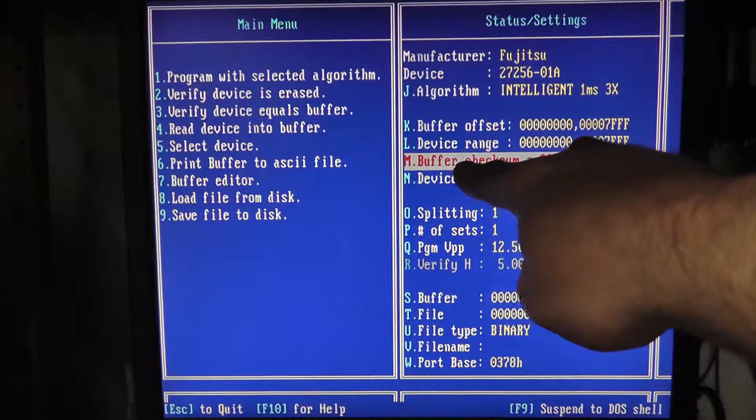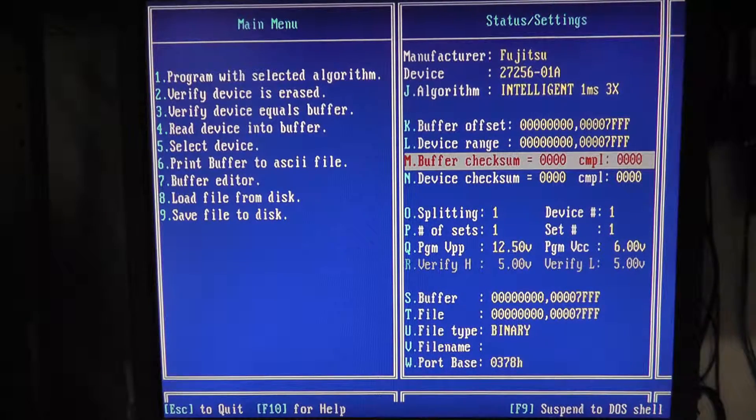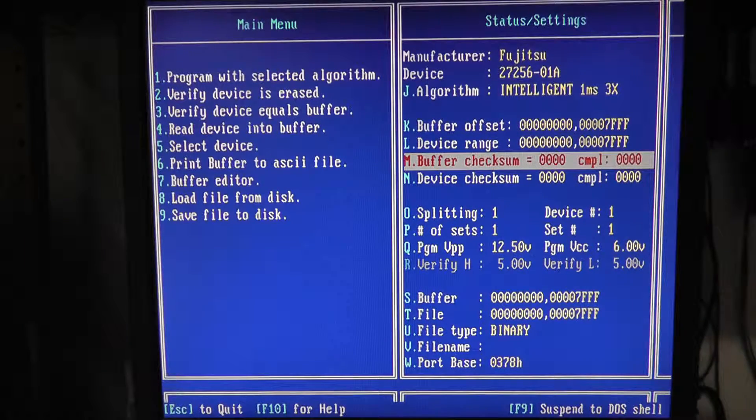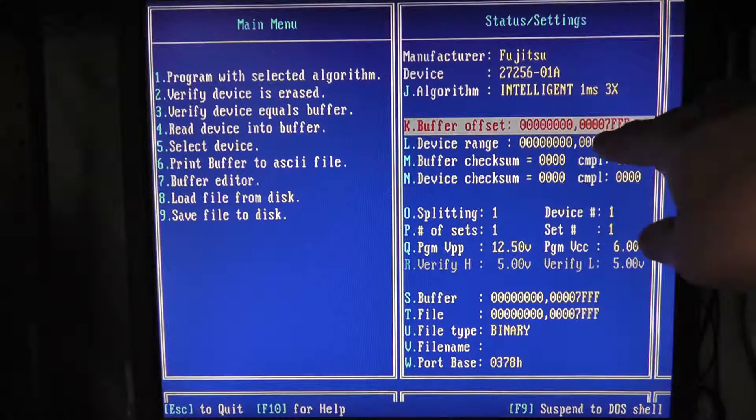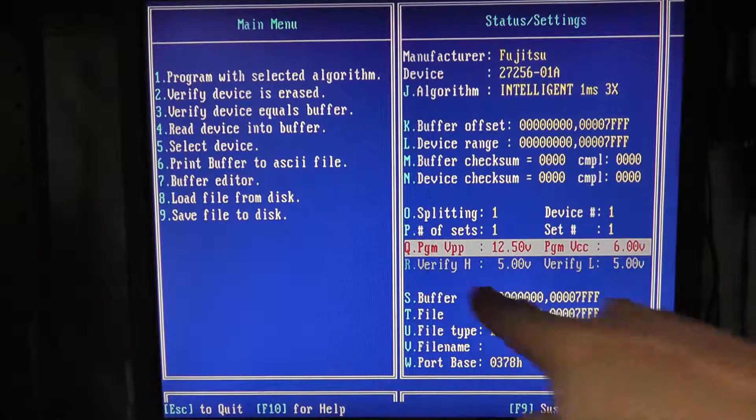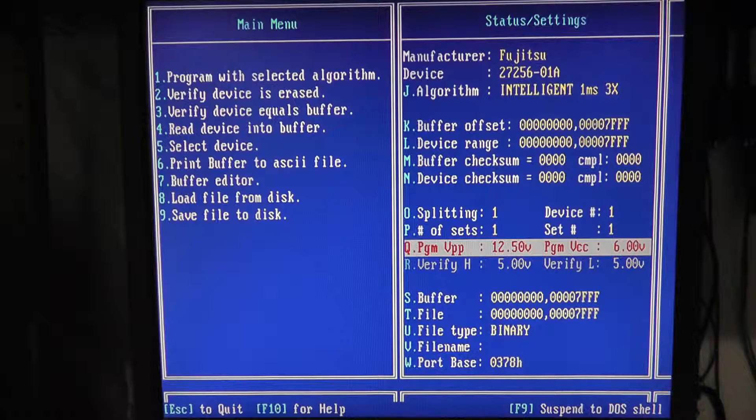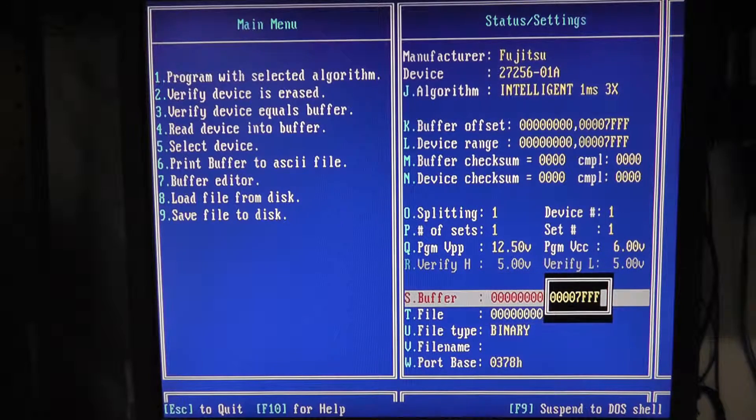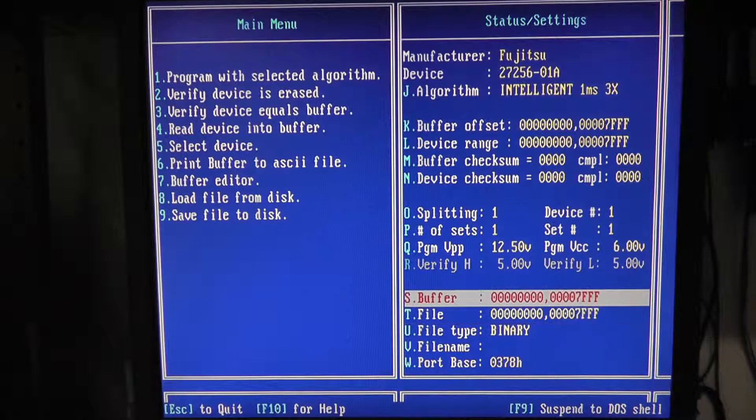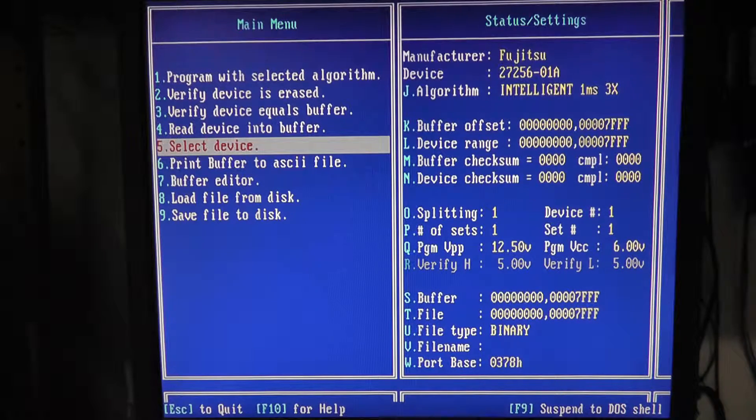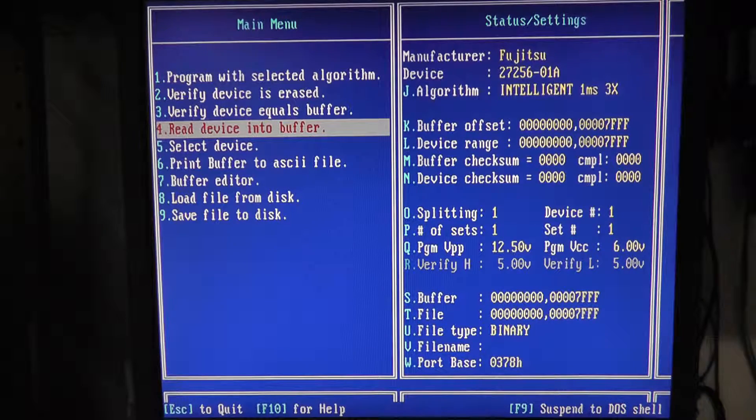The other thing is for the device checksum, it does show it right here, I didn't notice it before. You can check the checksum of whatever's in the buffer and the checksum of the device itself. And that is what you should see there is zero zero zero because we filled it with all zeros. And you see the buffer offset from zero zero zero to zero seven FF, and that's correct and everything. So the only thing you can't change here is it's grayed out is this verify voltage, which is good.